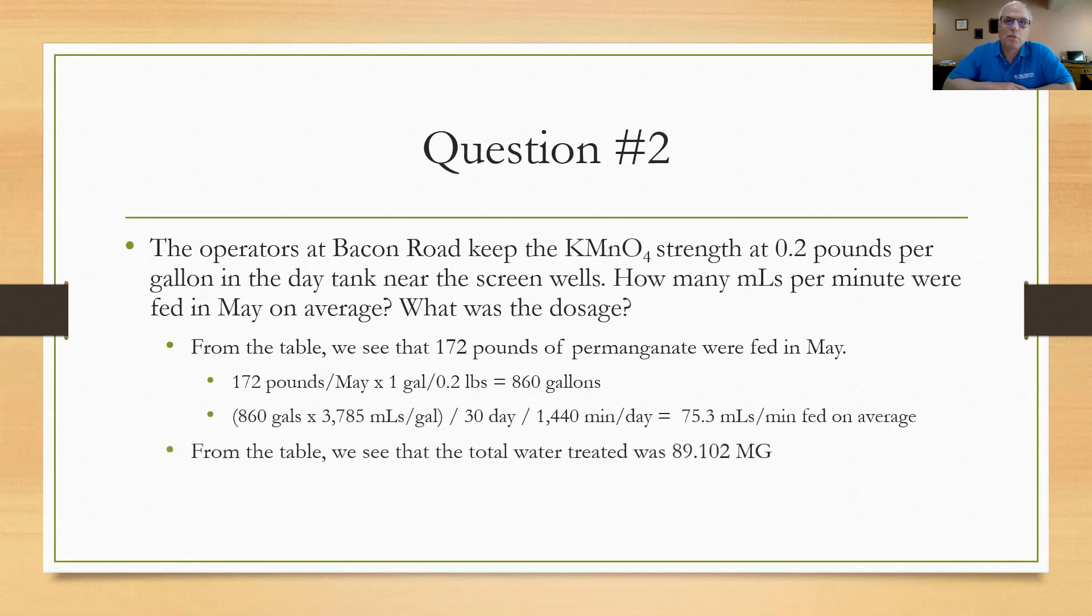So now the second part of that was what was the dosage? Well from the table I can see that the total water treated was listed as 89,000 or 89 million 102 thousand gallons or 89.102 million gallons, MG. I'm going to take that 172 pounds divided by the pumpage of 89.102. I see that we fed at a rate of 1.93 pounds per million gallons. And of course to convert that to milligrams per liter, I would divide by 8.34, and I come up with a dosage of 0.23 milligrams per liter dosage. Hope you got that one. Let's move on to question number three.